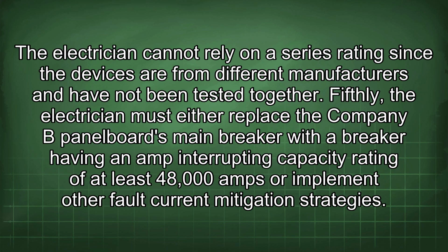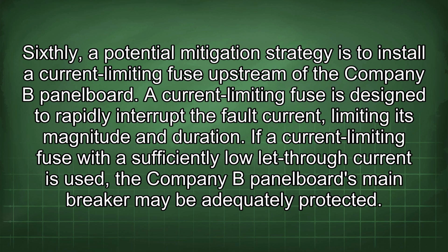The electrician cannot rely on a series rating since the devices are from different manufacturers and have not been tested together. Fifthly, the electrician must either replace the company B panel board's main breaker with a breaker having an amp interrupting capacity rating of at least 48,000 amps or implement other fault current mitigation strategies. Sixthly, a potential mitigation strategy is to install a current limiting fuse upstream of the company B panel board. A current limiting fuse is designed to rapidly interrupt the fault current, limiting its magnitude and duration.